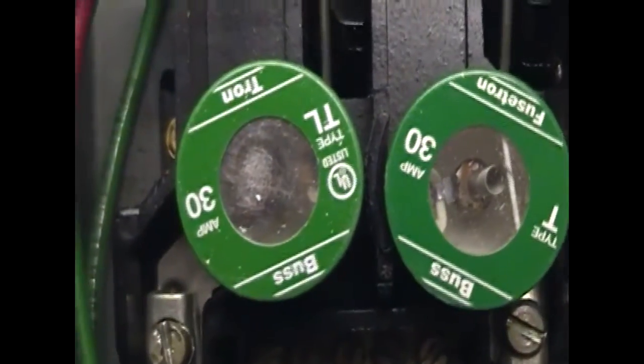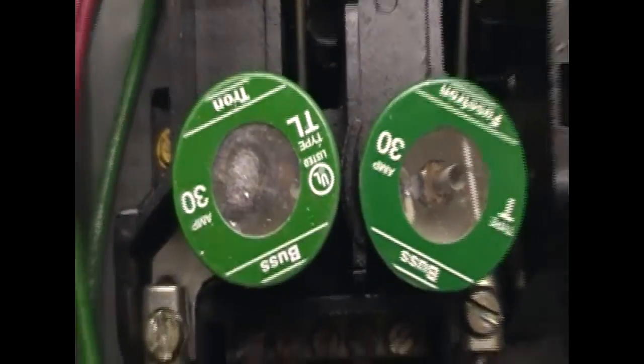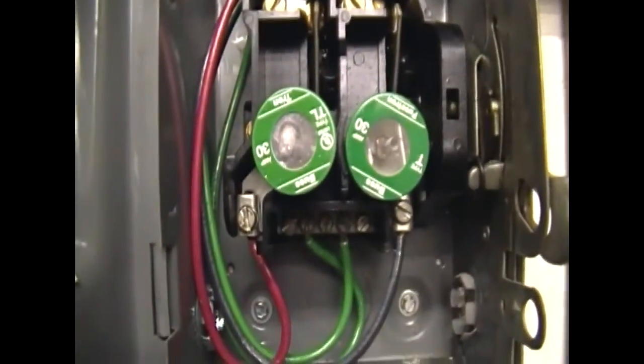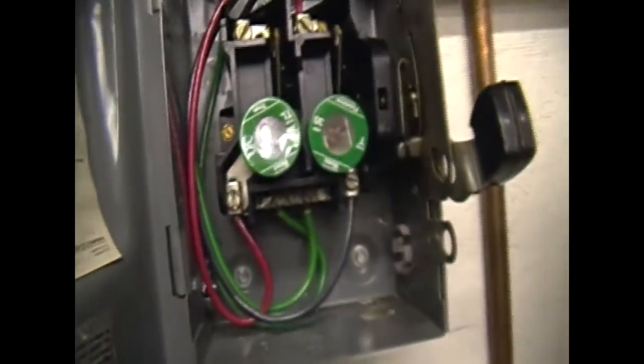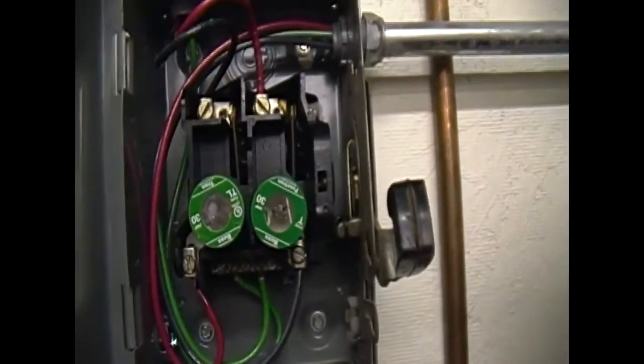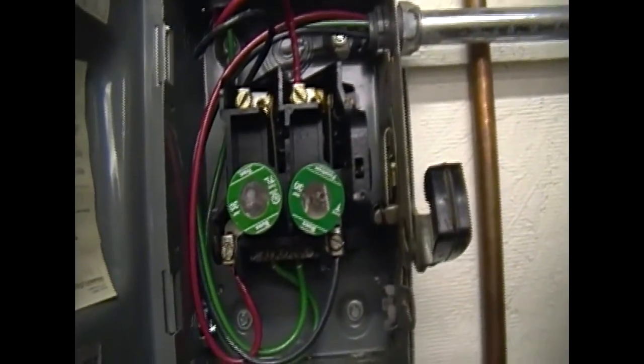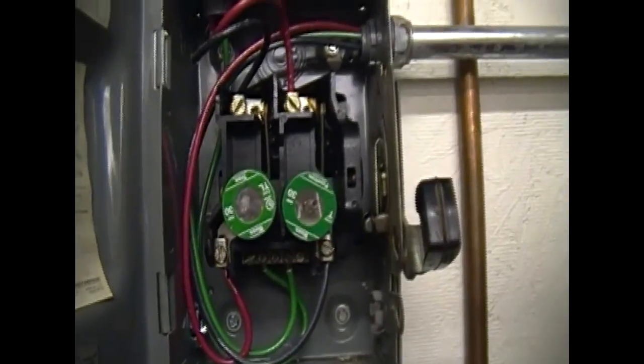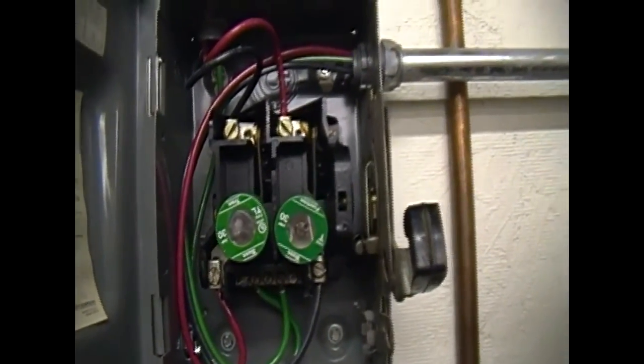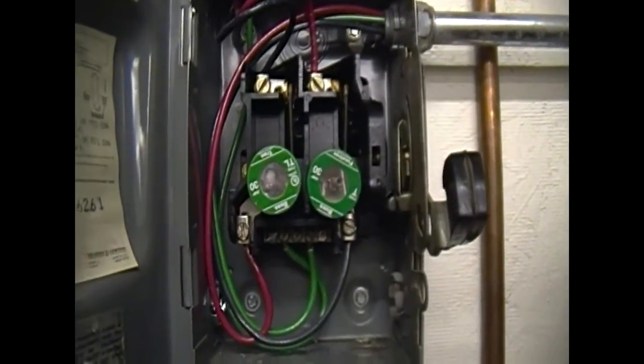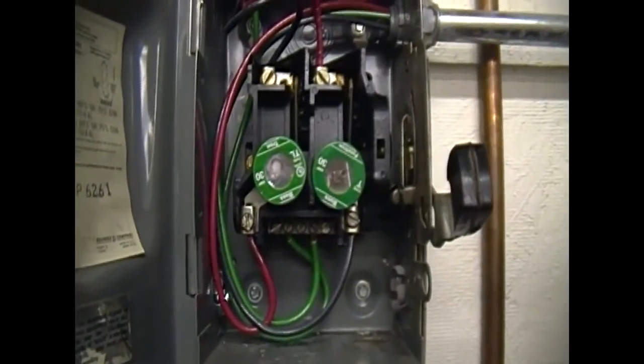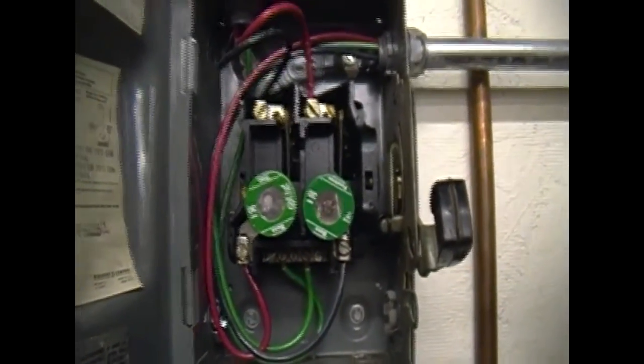Oh yeah. Okay, so here's the problem. The fuse here on the left leg is always the one that goes. So I suspect that I possibly have a loose connection. I talked to one of my maintenance guys at work, and they also said you can actually have a bad circuit breaker that'll cause that too.